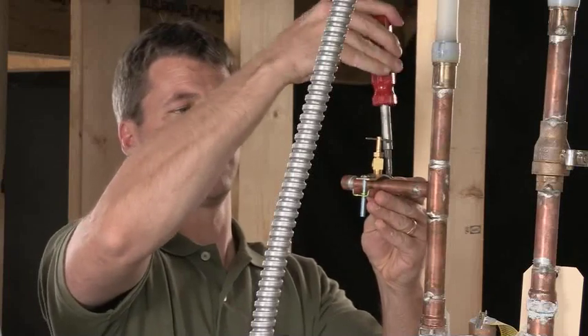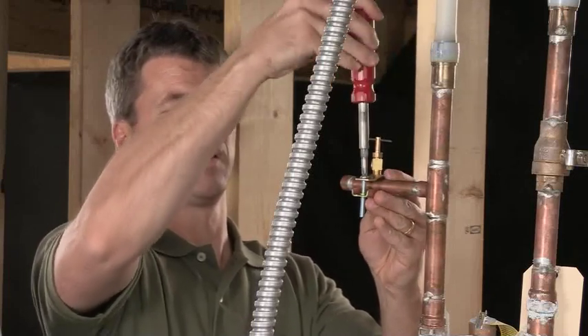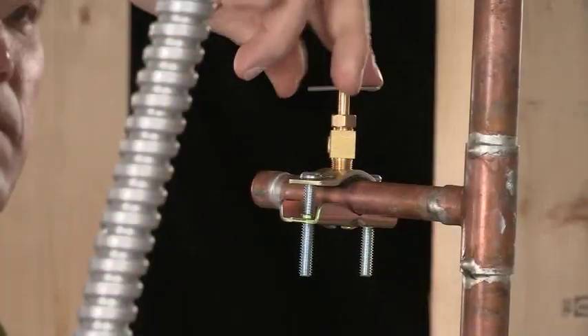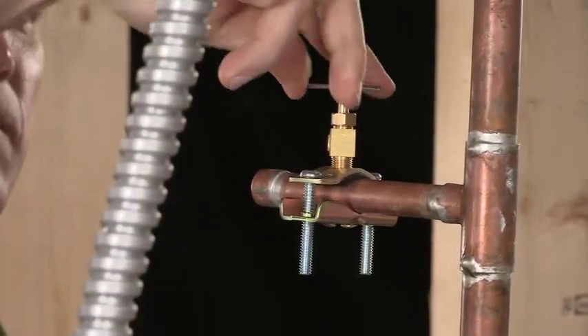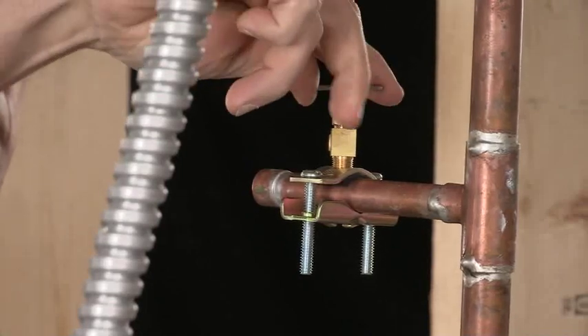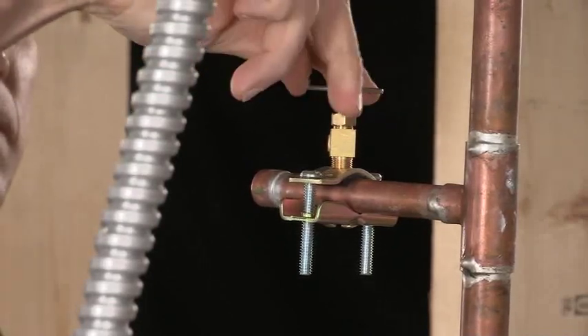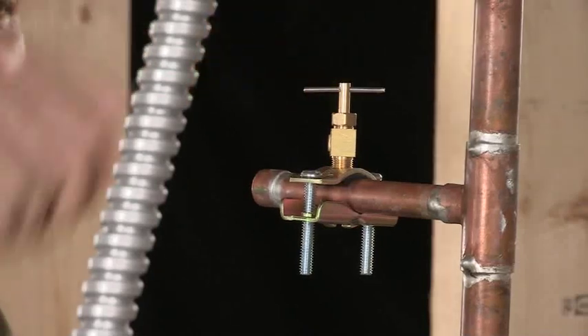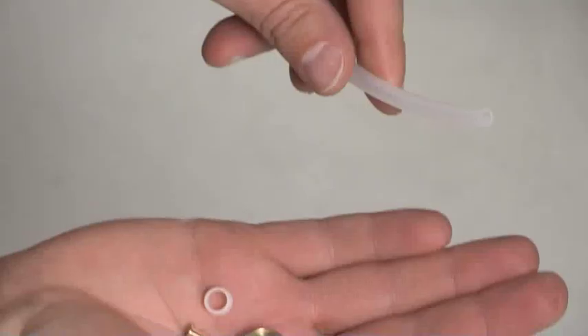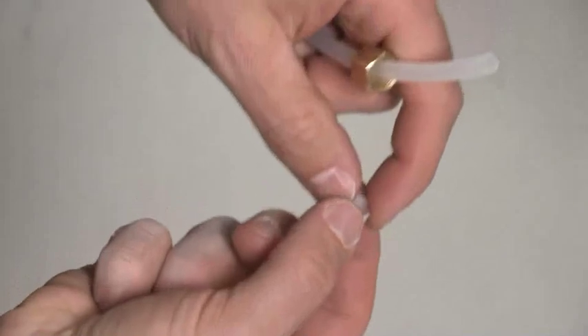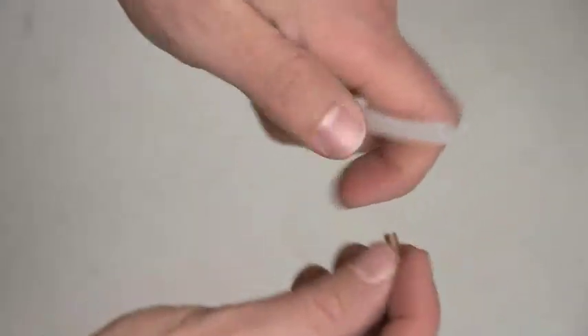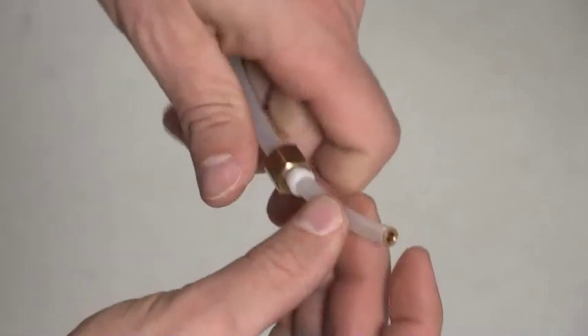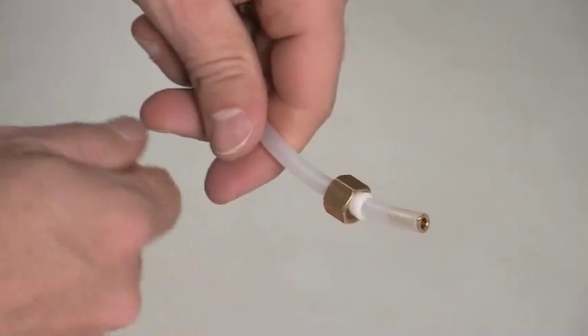Secure the saddle valve to the pipe as shown with the rubber gasket. Turn the handle on the top of the saddle valve clockwise until the needle pierces the water supply line. Leave the needle in this position until the humidifier is fully installed to prevent leaking. To make this connection to the saddle valve, prepare the tubing by sliding the brass compression nut over the tubing, placing the plastic compression ring over the tubing, and inserting the brass insert into the tubing with the wider portion facing outward.